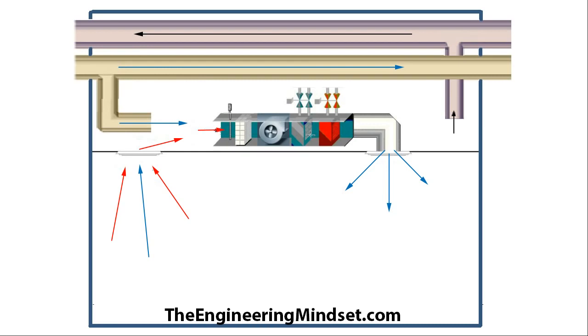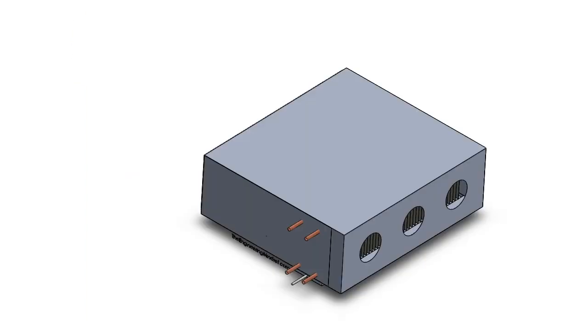The fresh air enters the fan coil unit and passes through a fan and filter. Once treated, it's pushed out through the diffusers into the space. This pushes the used air up, through the return grille, and back into the ceiling void, where it mixes again with fresh air. Some of the return air in the void is sucked out by a duct and pushed back out to atmosphere.